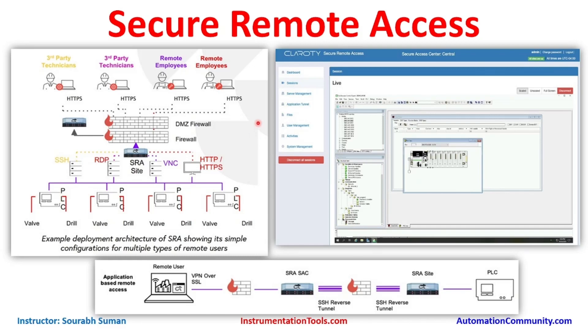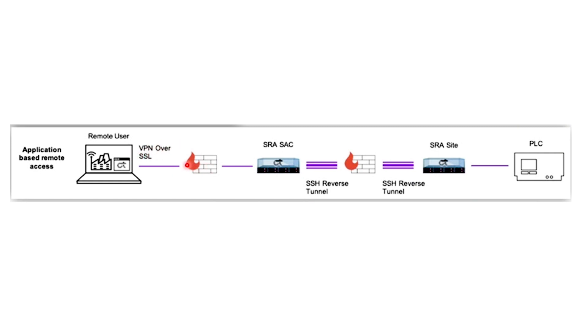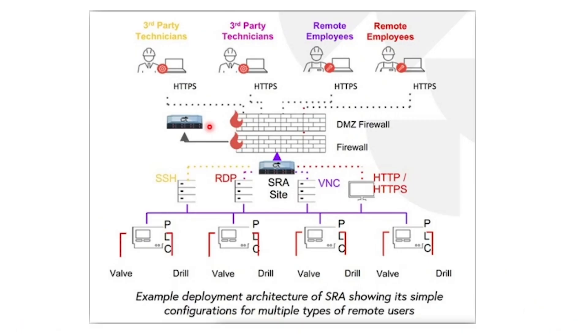Here we can see a solution for secure remote access from Claroty. In this architecture, a remote user opens an application, which sets up a VPN communication from the firewall using browser SSL functionality. This connects to a secure remote access server at the site, and an SSH reverse tunnel is extended to the SRA site. From there, the user can access PLCs. The deployment supports multiple PLCs with SSH, RDP, VNC, and HTTP communications, all enabled through the secure remote access server.